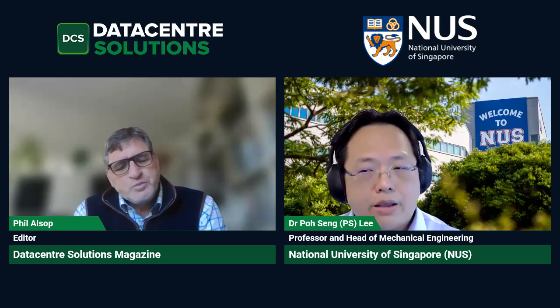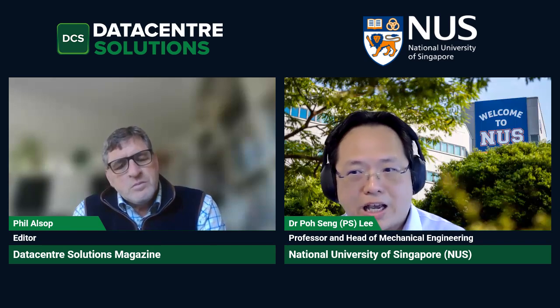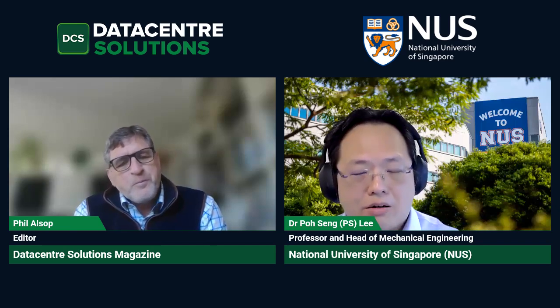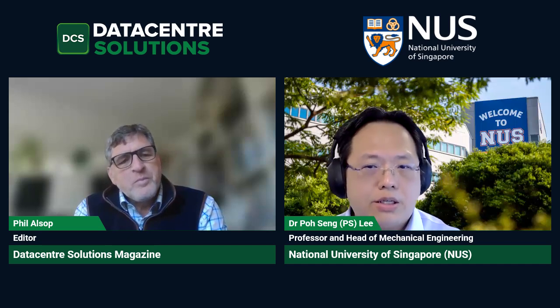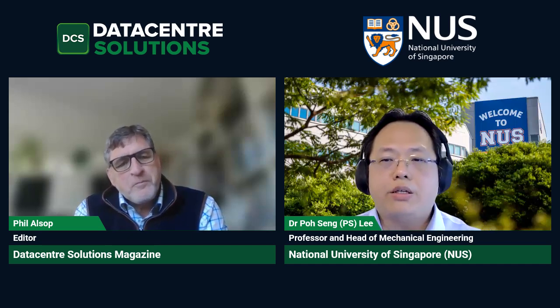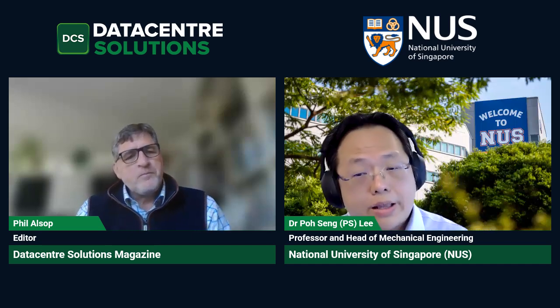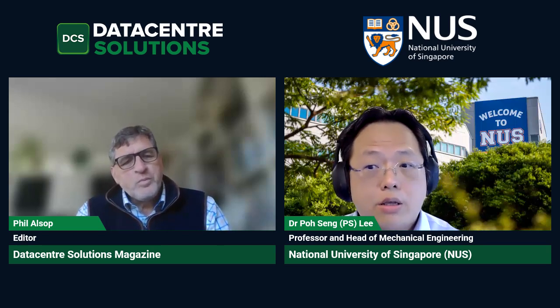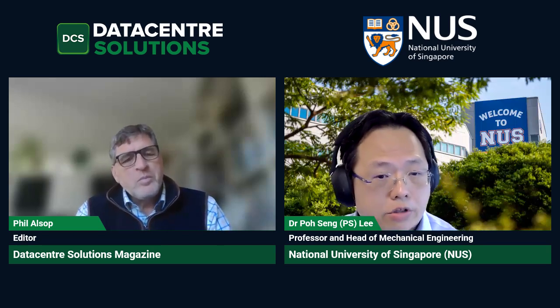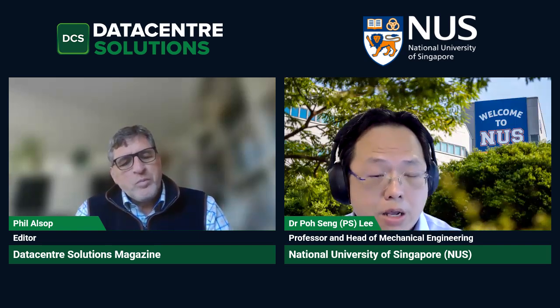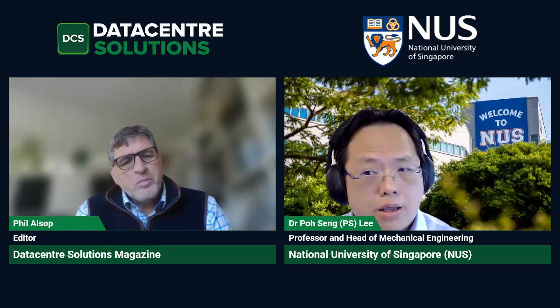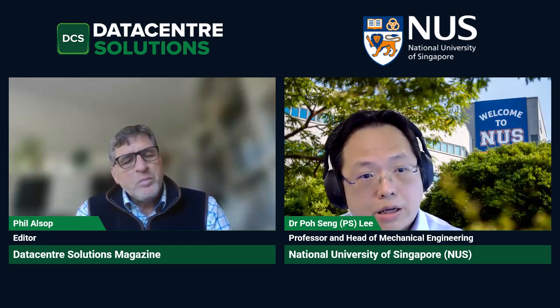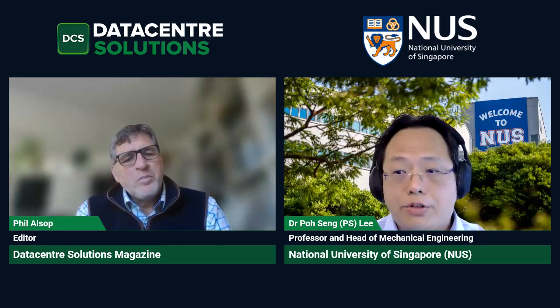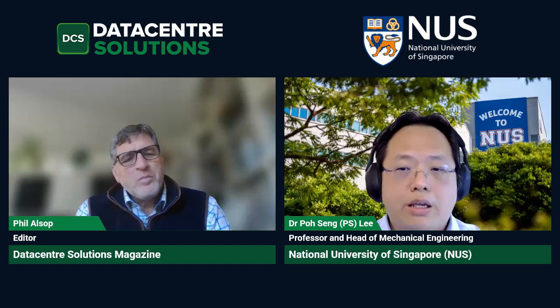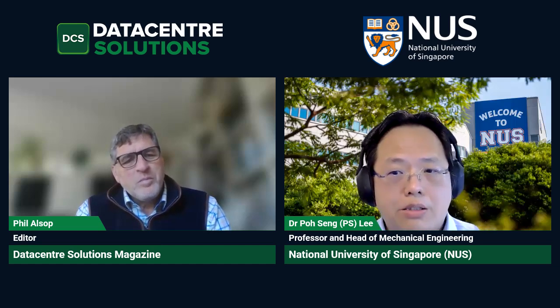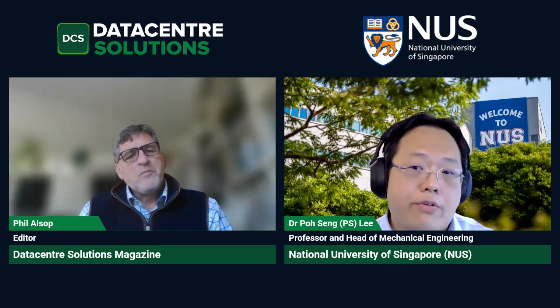We're going to link the delta T in millikelvins or the delta P in millibars - the pressure decisions at the cold plates - because that can actually translate to hundreds of kilowatts at the plant, especially with the hundreds of megawatts, and in time gigawatt, data centers we're talking about. That will allow the operator to have the line of sight into how two-phase stops being exotic and starts to become an economic design variable.